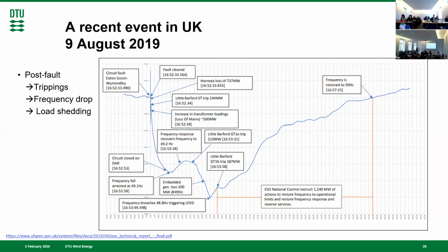This is how the frequency developed: it started falling, and as more generation was lost, it dropped to a level where they had to start disconnecting load to limit the drop in frequency and prevent a total blackout of the system. What came out publicly was that this was due to instabilities or oscillations in the electrical systems, caused by improperly tuned controllers and interaction between the wind turbines and the grid connection point.